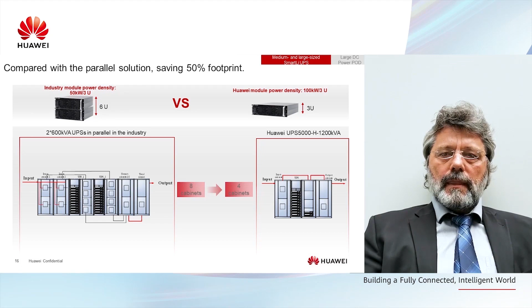On the next slide you see the top view arrangement of 2 solutions including battery space in a typical arrangement. The right side uses valve regulated lead acid batteries on racks. Together with the 2 × 600 kVA UPSs, a footprint of 52 square meters is required. The 1.2 MW Fusion Power is combined with a Huawei SmartLi battery. The footprint required is now only 25 square meters, which is a saving of 50%.